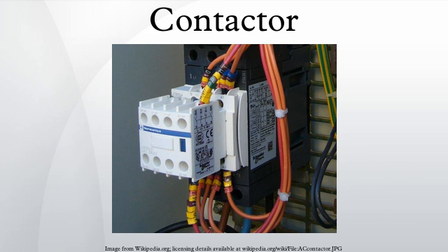The contacts move past each other after initial contact in order to wipe off any contamination. Arc suppression. Without adequate contact protection, the occurrence of electric current arcing causes significant degradation of the contacts, which suffer significant damage. An electrical arc occurs between the two contact points when they transition from a closed to an open state, or from an open to a closed state.